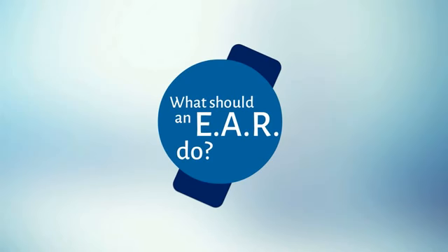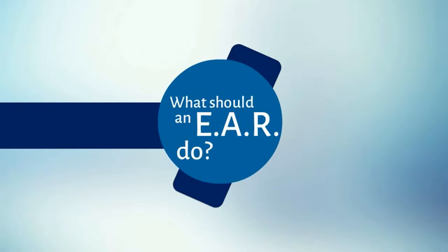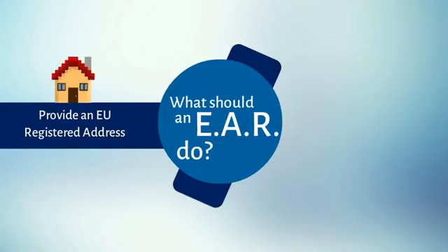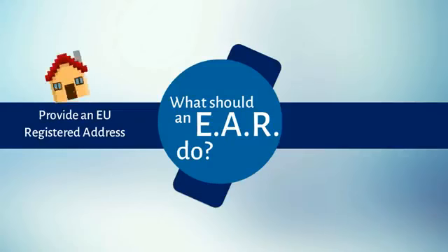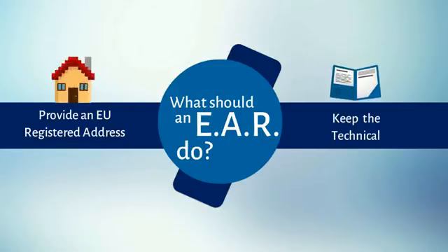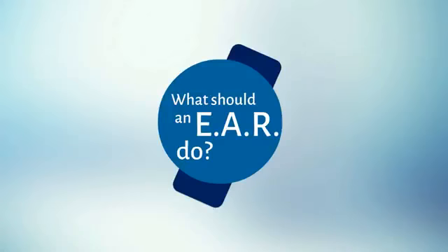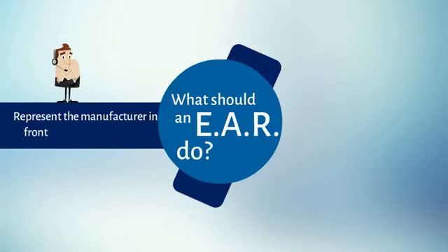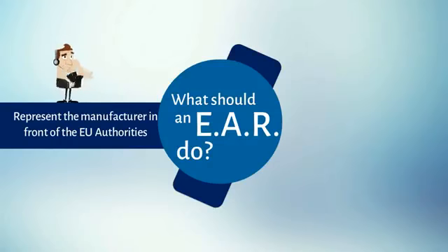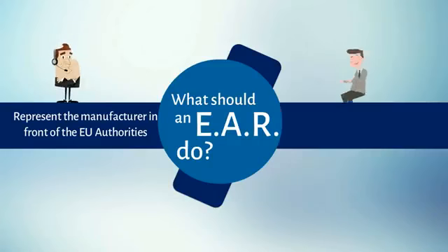What should an EAR do for the manufacturer? The EAR should: 1. Provide the manufacturer with a registered address in the EU to be mentioned on the product packaging. 2. Keep, at his registered address in Europe, the technical documentation available for inspection by the EU authorities. 3. Maintain constant availability to represent the manufacturer in front of the EU Commission, EU authorities, EU certification bodies, and the European users.